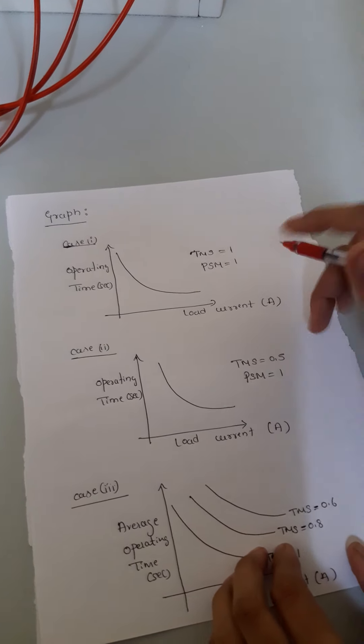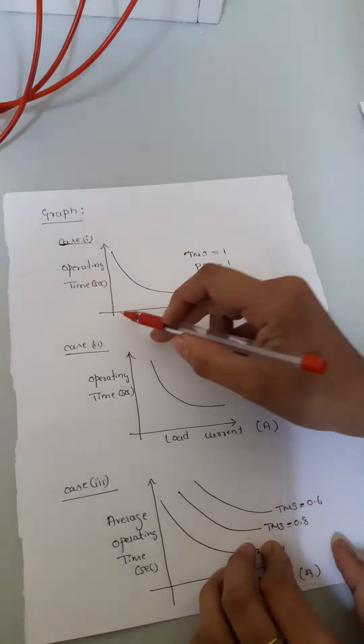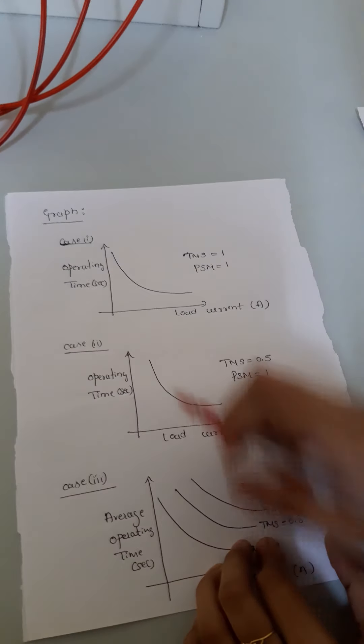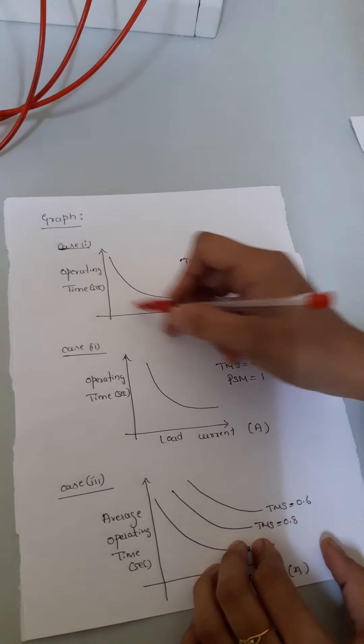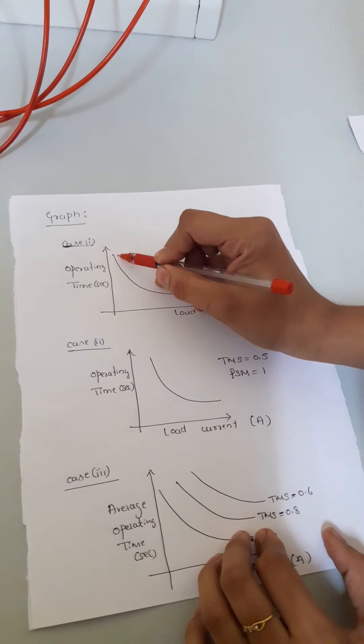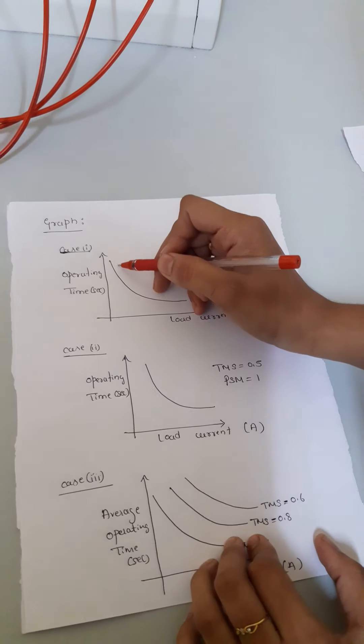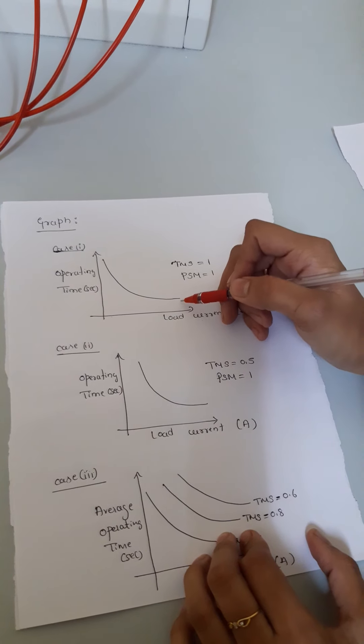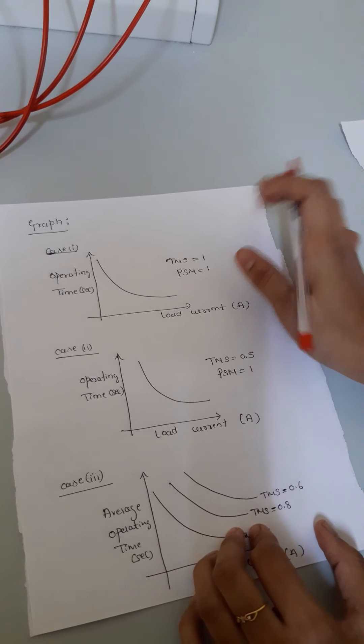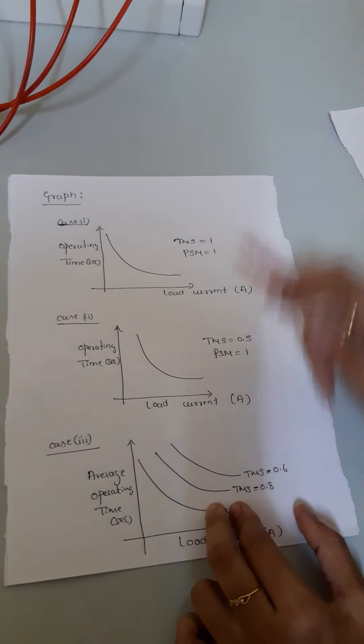From case 1 and case 2, after taking the values, we need to plot two graphs: on the x-axis, the load current, and on the y-axis, the operating time in seconds. The load current and operating time are inversely related — the lower the current, the more the operating time; as the current increases, the time taken for the relay keeps reducing. This is just like IDMT characteristics, or Inverse Definite Minimum Time characteristics. This is the graph for case 1 and this is the graph for case 2.